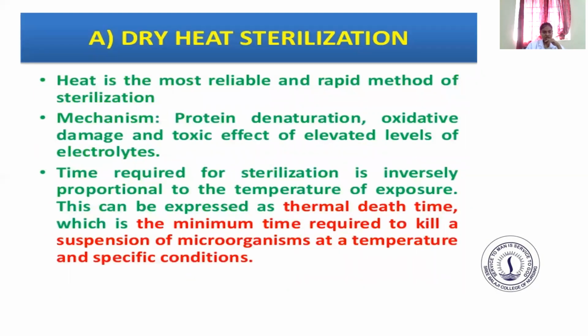And then dry heat sterilization. This is the most reliable and rapid method of sterilization. In mechanism, protein denaturation, oxidative damage, and toxic effect of elevated levels of electrolytes. Time required for sterilization is inversely proportional to the temperature of exposure. This can be expressed as thermal death time, which is the minimum time required to kill a suspension of microorganisms at a temperature and specific condition.